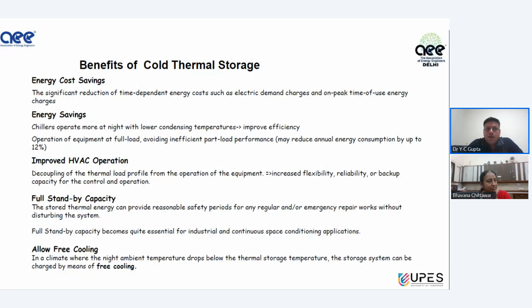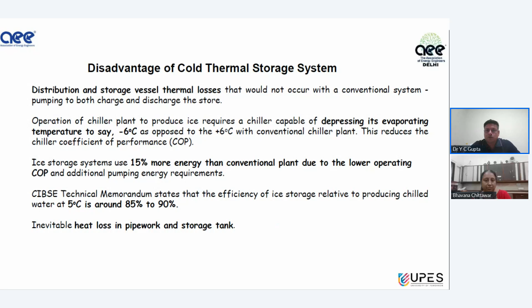There are disadvantages too, but those are small. Ice storage systems use 15% more energy than conventional plants due to the lower operating coefficient of performance. So if our chiller is efficient enough, we get more benefit out of it. Overall efficiency is around 85 to 90%, because we lose some energy in the pipelines, heat exchangers, and air conditioners.